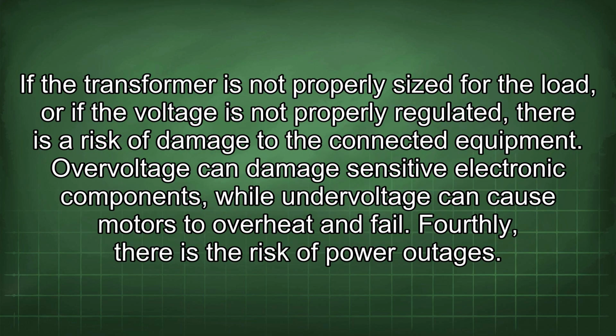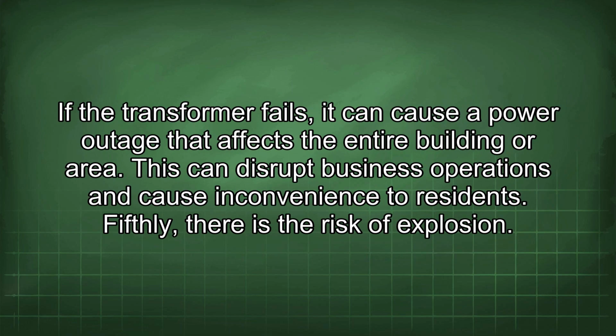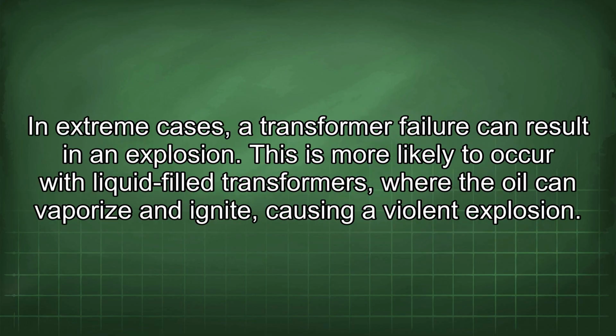Thirdly, there is the risk of equipment damage. If the transformer is not properly sized for the load, or if the voltage is not properly regulated, there is a risk of damage to the connected equipment. Overvoltage can damage sensitive electronic components, while undervoltage can cause motors to overheat and fail. Fourthly, there is the risk of power outages. If the transformer fails, it can cause a power outage that affects the entire building or area. This can disrupt business operations and cause inconvenience to residents. Fifthly, there is the risk of explosion. In extreme cases, a transformer failure can result in an explosion. This is more likely to occur with liquid-filled transformers, where the oil can vaporize and ignite, causing a violent explosion.